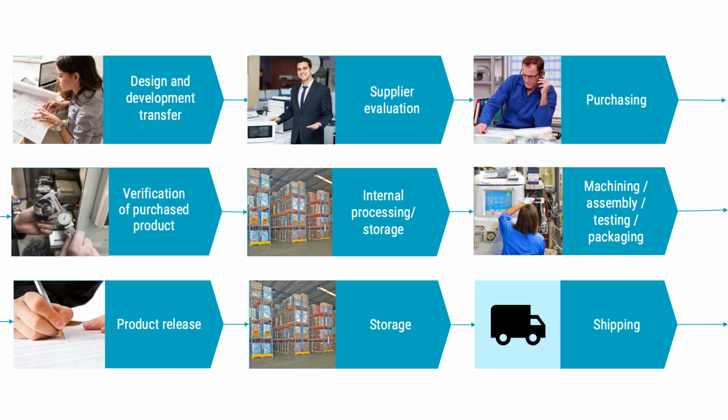The requirement related to the PRRC in the MDR is that the PRRC is responsible for ensuring that the conformity of the device is appropriately checked in accordance with the quality management system under which the devices are manufactured. And the requirements of the QMS do not only include product release, but rather a lot of different activities. This means that the PRRC needs to have a good understanding of the manufacturer's QMS, and he or she needs to have access to supplier evaluation records and purchasing documentation also, just to mention a few.